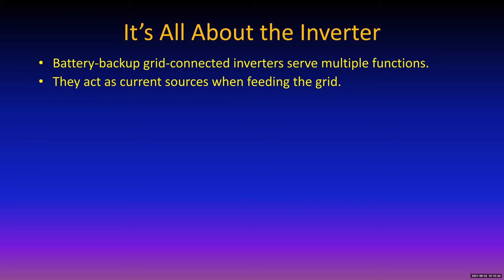The reason for that is when you connect a new source of electricity into the grid and flip that switch, that source has to be exactly in phase with the grid power. Because if not, either the solar system or a small generator, if it's a rotating generator, somebody's generator gets hurt because that's an incredible torque trying to bring that source back into sync with the grid.